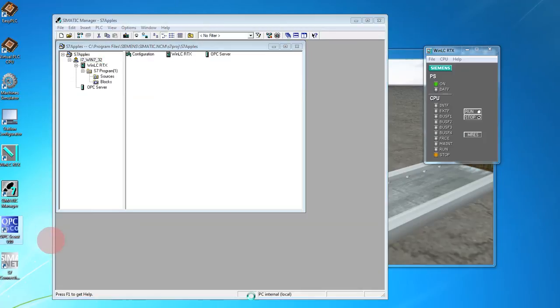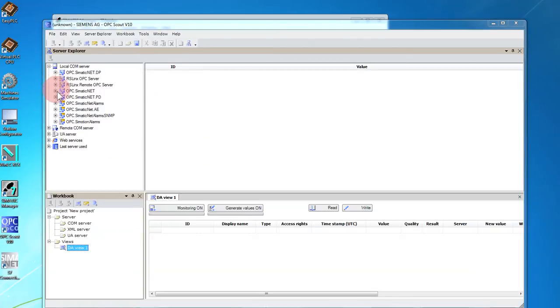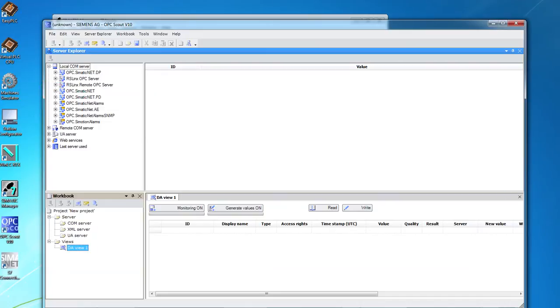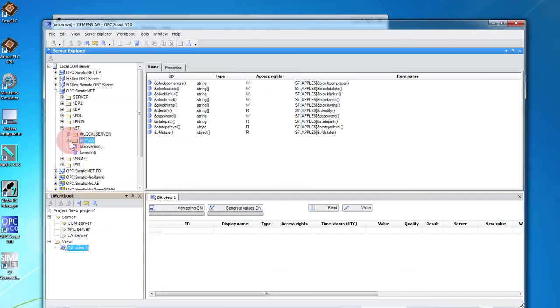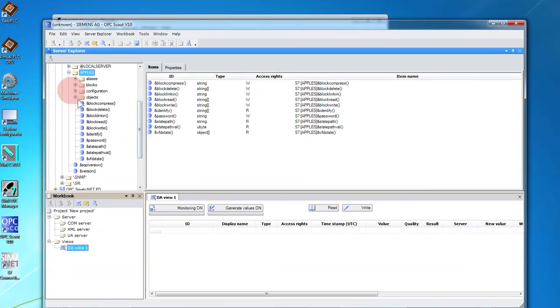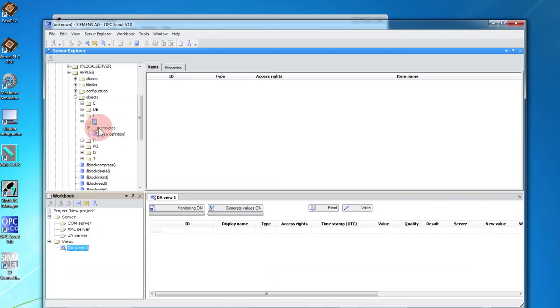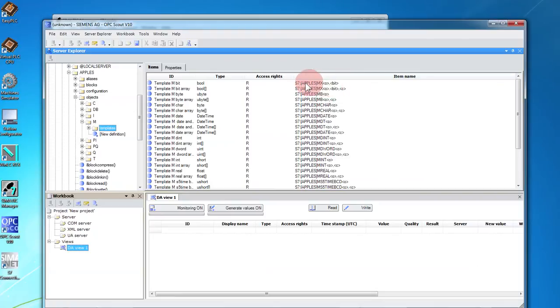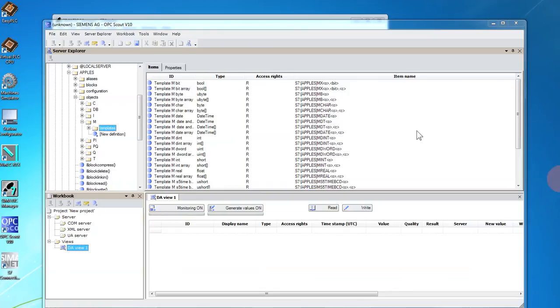Bring up opcscout. Now we can browse the OPC SIMATIC NET server. All we care about is s7 and there's our apples topic. Let's browse this open a little bit more. Look at our objects we care about m. Click on templates, this shows us here the format we need to make our tags for the easy plc opc. Notice it's mx not just m0.0 and our topic is going to be s7 colon apples. We don't need to set anything up in here.